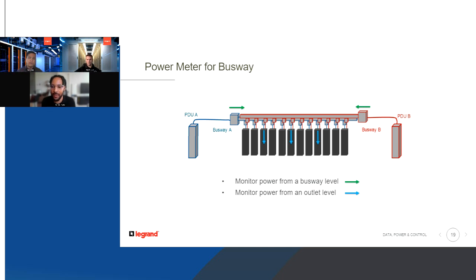This just shows where we can monitor on the busway. There are two locations: one is at the infeed, where it monitors the aggregate current of all loads traveling through the bus, and we can also monitor at an outlet level, specifically how much current and power is traveling through the outlet into the rack or load being powered. Nick, is the busway selectively sectionalized, like in the case of a fault in the bus itself? Could it be remotely, partially isolated as well?